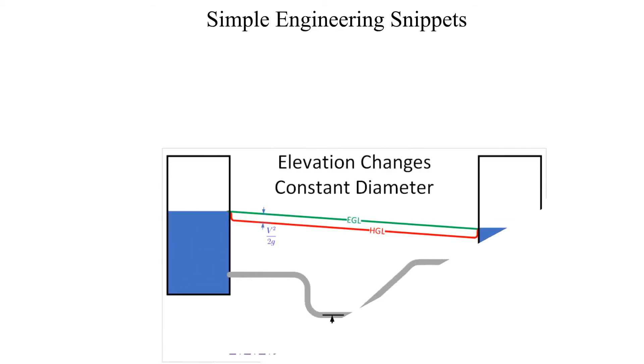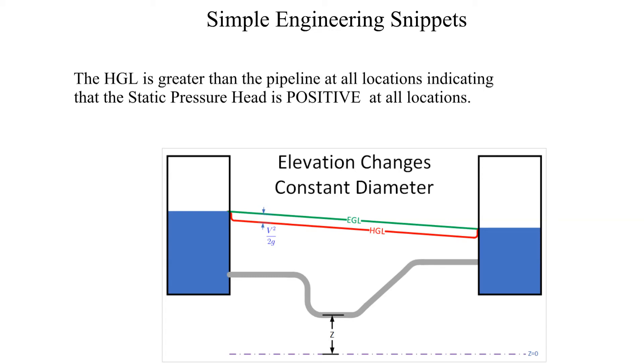Now let's consider a constant diameter pipeline with changing elevations. In this example, the hydraulic grade line is greater than the pipeline at all locations indicating that the static pressure head is positive.